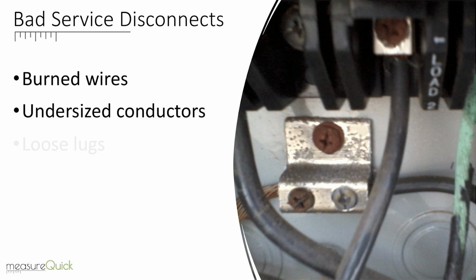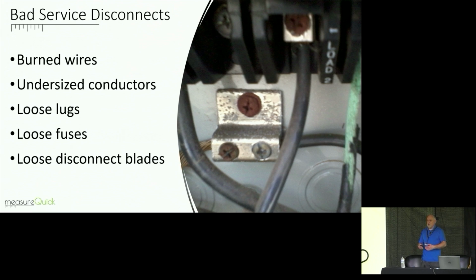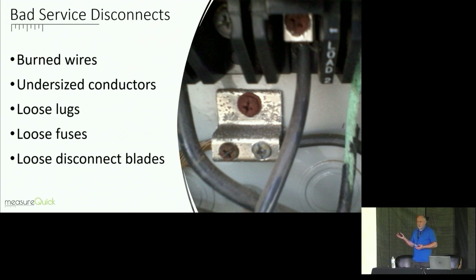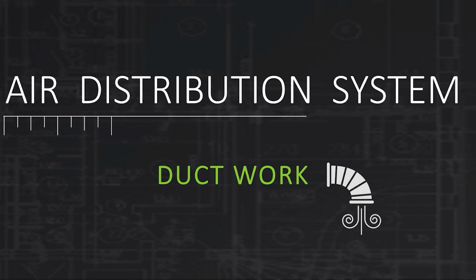And again, undersized conductors, loose lugs, loose fuses. So many guys will go out and they'll see a compressor's hard to start, and they'll put a hard start kit on that, or they'll put a soft start kit on that, and they're fixing a symptom, not the problem, right? So we've got to make sure we're addressing those things.